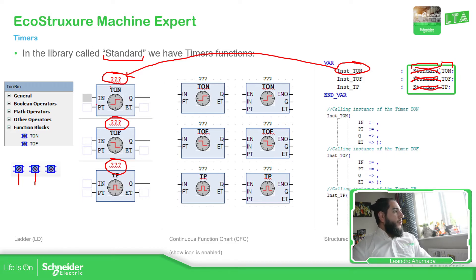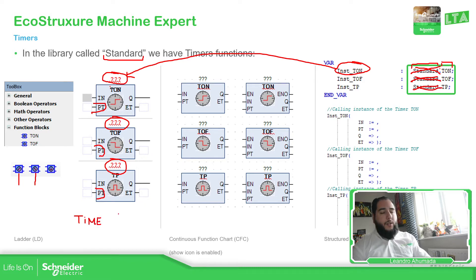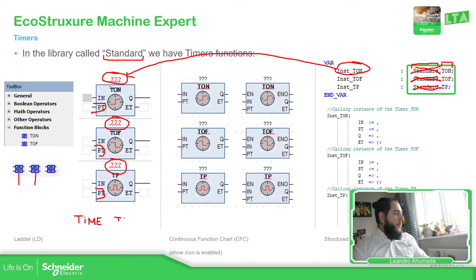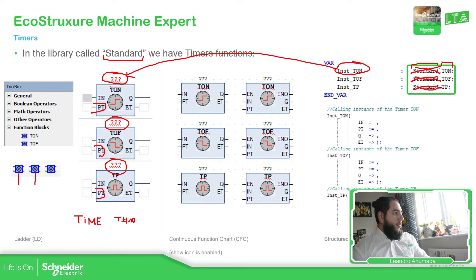Once you add it in the local or global variable list, you can use the instance name you defined in the question marks and then use the function block. Something important is this input — the PT. This PT input is defined as a time variable. The time variable has a different structure. In order to define a fixed time, you just need to use T# and then the unit of time. For example, if it is 10 seconds: T#10s.